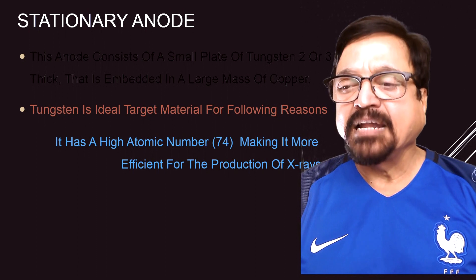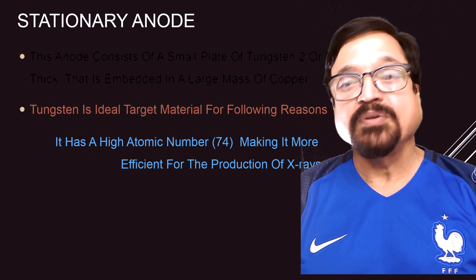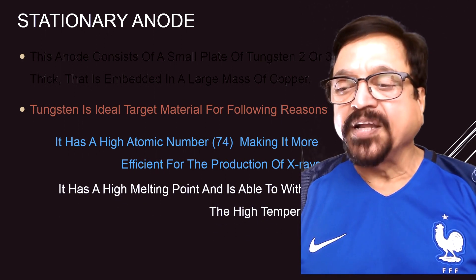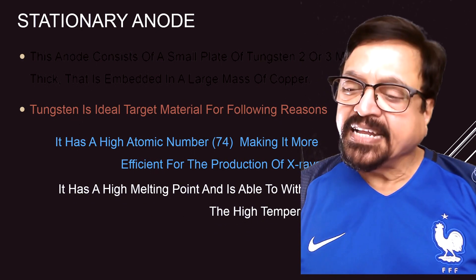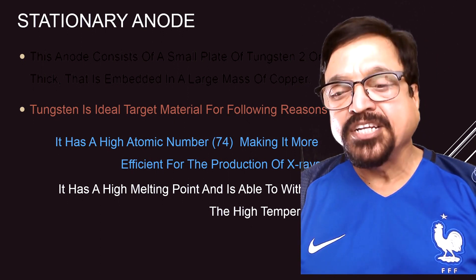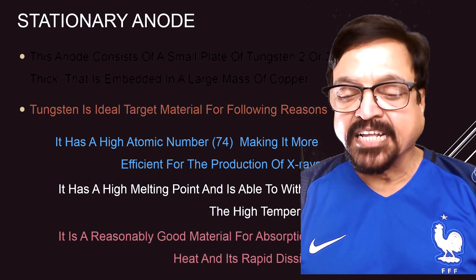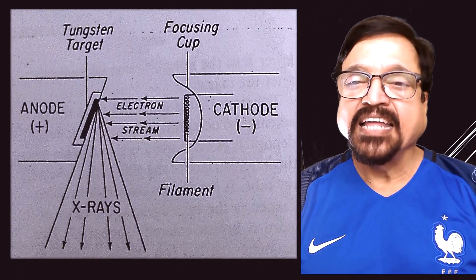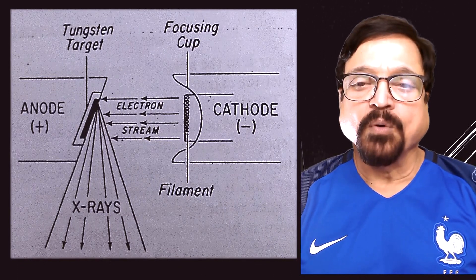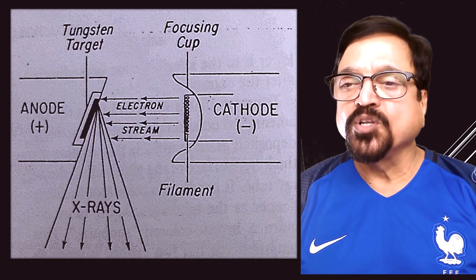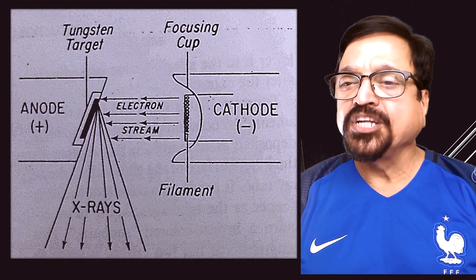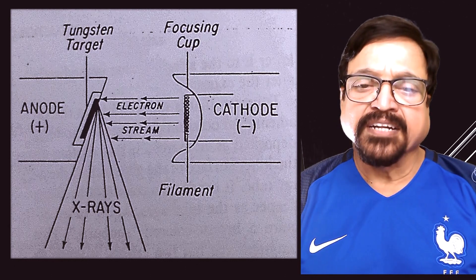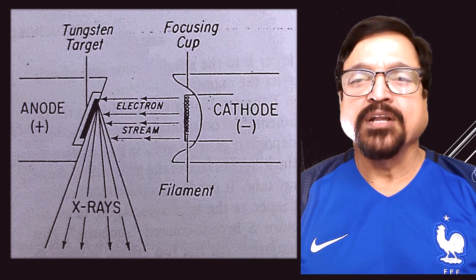Tungsten is the ideal target material for the following reasons. It has a high atomic number of 74, making it more efficient for the production of X-rays. It has a high melting point and is capable of withstanding the temperatures generated. It is also a reasonably good material for absorption and rapid dissipation of heat, and copper provides additional help. Here we can see the anode of tungsten and the cathode which is negatively charged, with the focusing cup streamlining the electrons so they bombard the tungsten target and the energy is converted into X-rays.